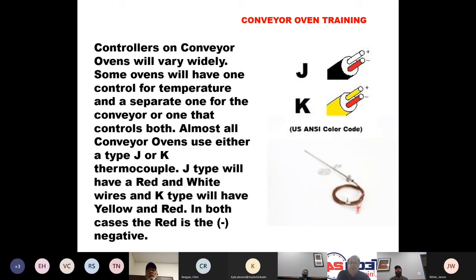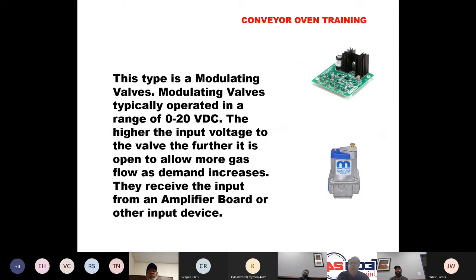Most of our controllers... The text question is on the modulating valve: how does the voltage work? The higher the input voltage to the valve, the further it is open, so the more gas flow we get. As that voltage is decreased, the valve closes and we get less gas flow.